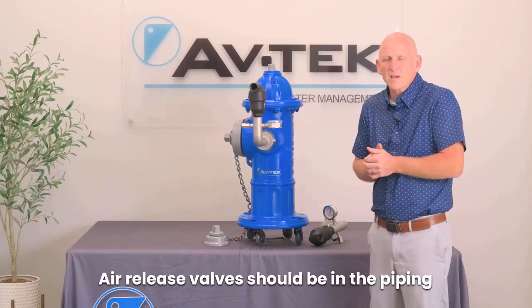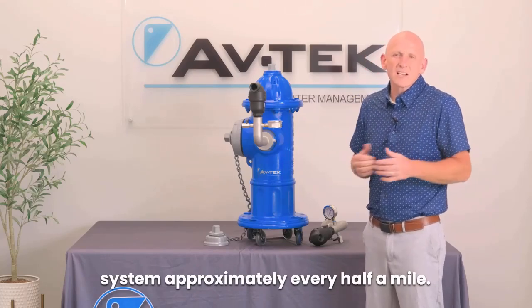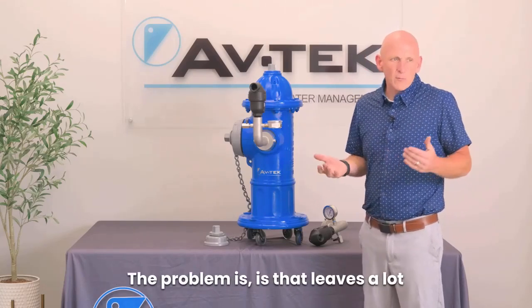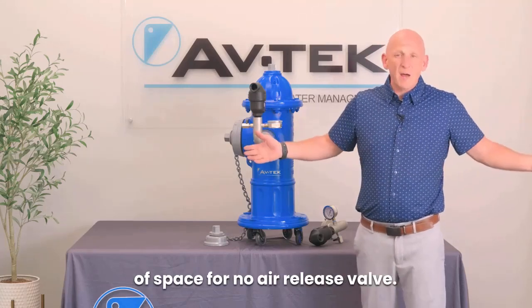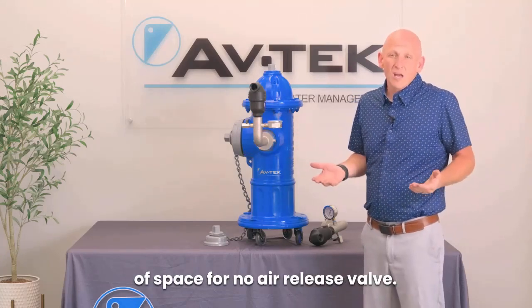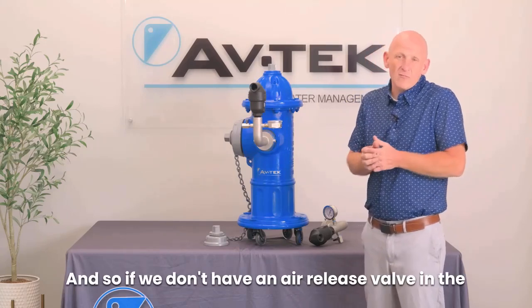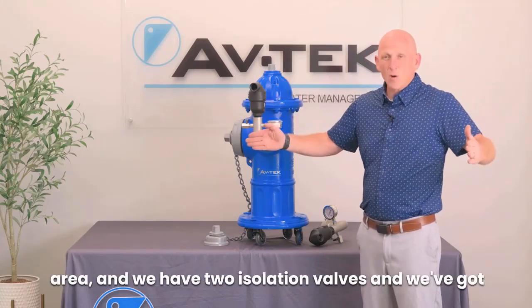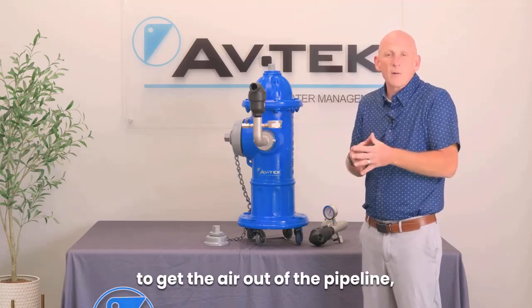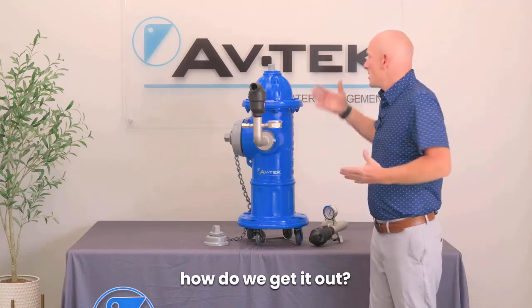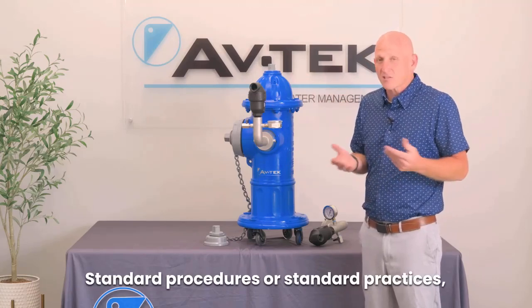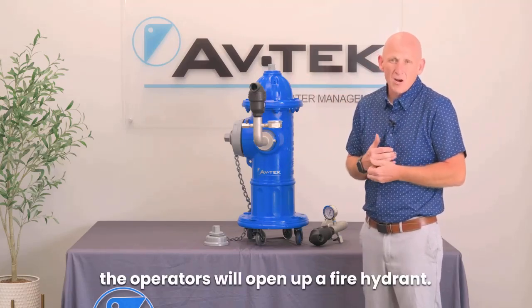Air release valves should be in the piping system approximately every half a mile. The problem is that leaves a lot of space with no air release valve. And so if we don't have an air release valve in the area and we have two isolation valves and we've got to get the air out of the pipeline, how do we get it out? Standard procedures and standard practices is the operators will open up a fire hydrant.